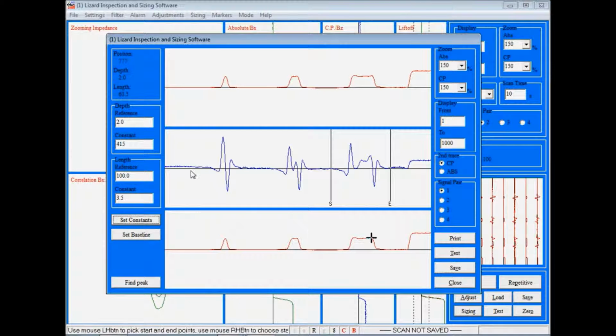This has generated for me a constant number, in this instance 415. This constant number is then used in the system's algorithms for future sizing operations using this probe. That is a very quick way of setting the depth sizing for the Lizard system.